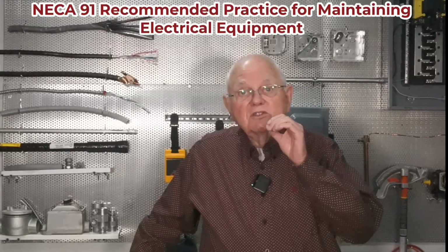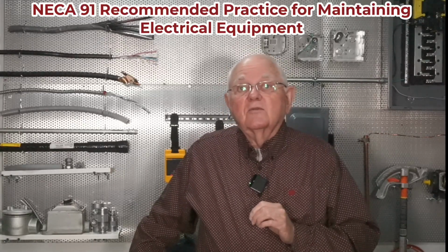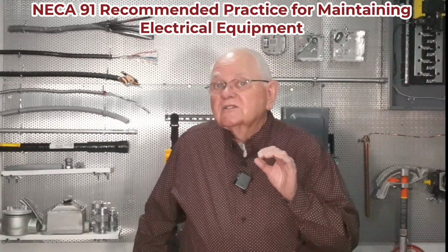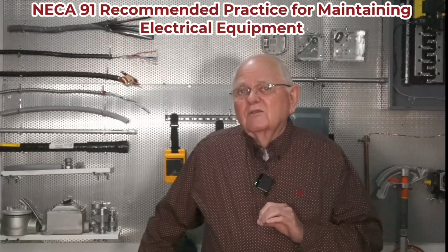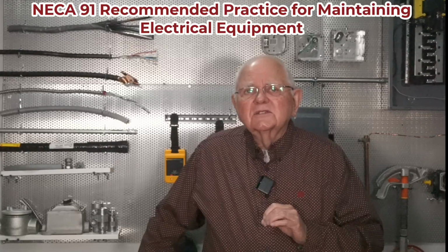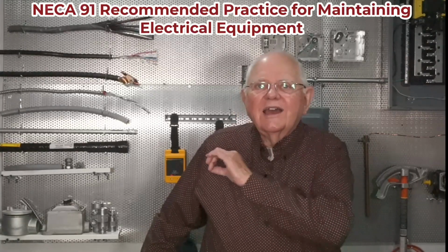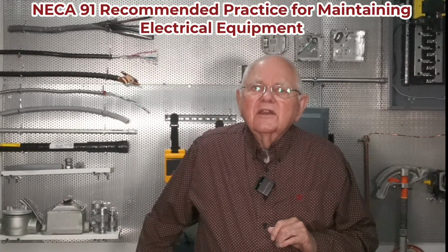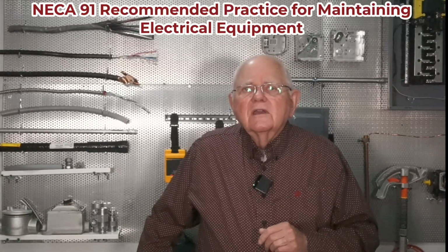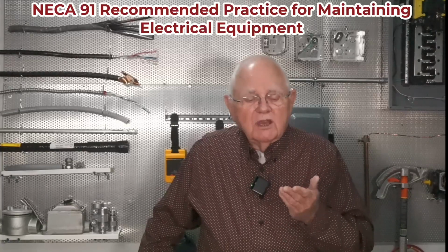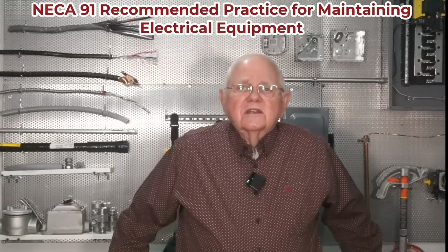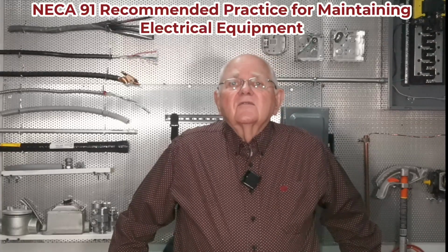Very important. It talks about safety in battery systems once again. We've already mentioned some information in Chapter 14 on that. It talks about that SF6 gas, that we use for insulation in some of our medium and high voltage equipment like breakers and switches. That's sulfur hexafluoride, and it can be very caustic if it leaks out of the system and forms a white powder. And I can have enough moisture, understand, just in my dry fingers, that when I touch it I can make an acid out of it, and of course that can create injuries as well. So anyway, covers a lot of information then.